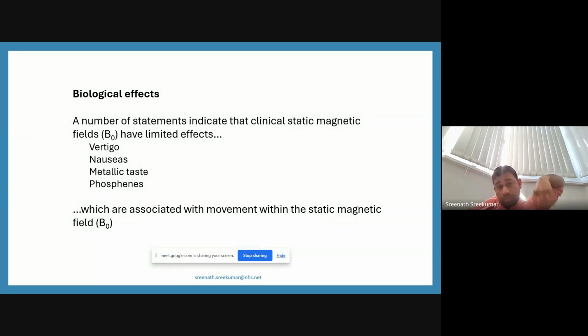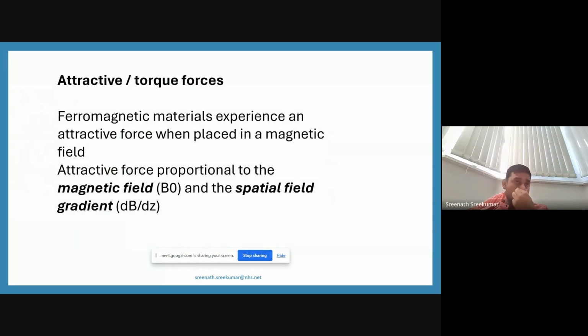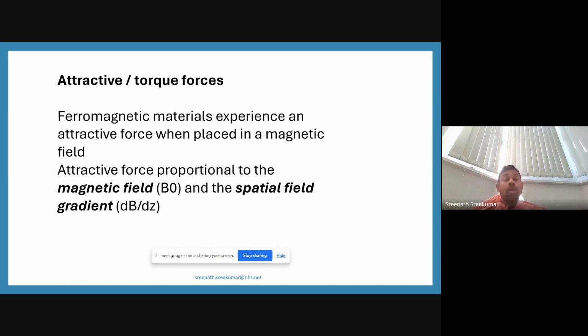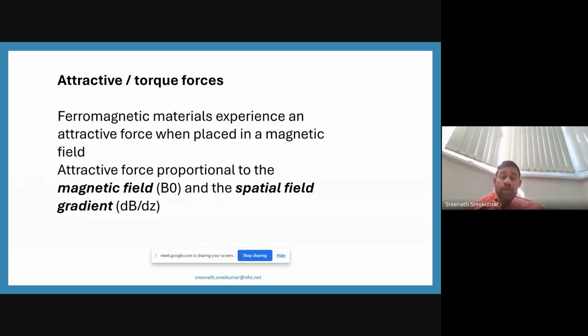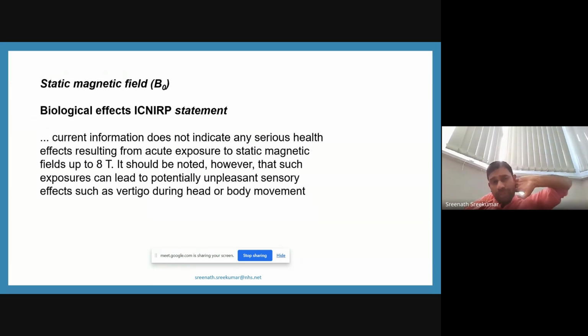And also patients may experience peripheral nerve stimulation. Some of the scans will be experienced as peripheral nerve stimulation. Also attractive and torque forces: ferromagnetic materials going into the MRI environment or spatial gradient will have a strong attractive force toward the machine. And from the ICNIRP statement, the International Commission on Non-Ionizing Radiation Protection, there are no serious health effects up to exposure to an 8 Tesla magnetic field, and no serious health issues are denoted for the personnel who are being scanned or who enter the MRI room. So only some vertigo, head or body movement, or unpleasant sensory effects will be there.